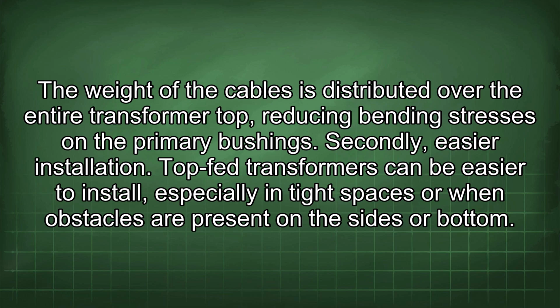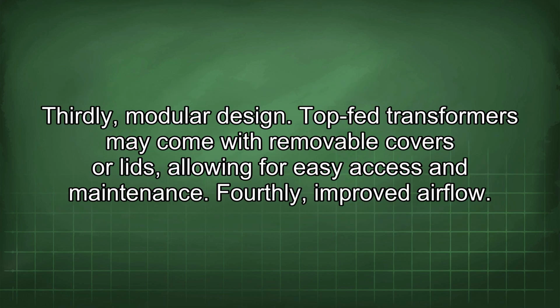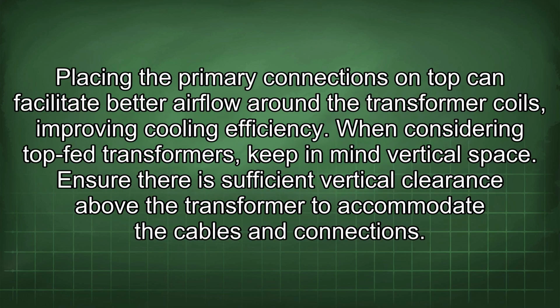Top-fed transformers can be easier to install, especially in tight spaces or when obstacles are present on the sides or bottom. Thirdly, modular design. Top-fed transformers may come with removable covers or lids, allowing for easy access and maintenance. Fourthly, improved airflow. Placing the primary connections on top can facilitate better airflow around the transformer coils, improving cooling efficiency.